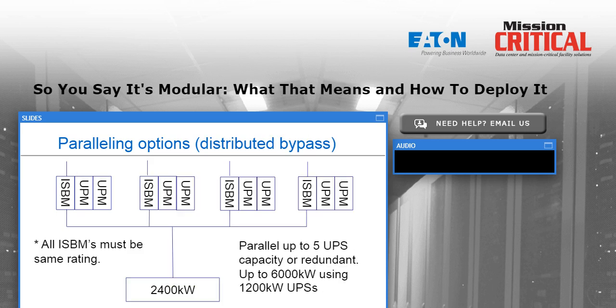Now this last slide here is a block diagram of a distributed bypass system where each one of the 4 UPSs that are shown across this slide has its own independent static switch. So this is the most common way of doing parallel systems for redundancy or capacity today around the world. It does put it in a position where each UPS system does need to be the same size, but these kind of systems, especially if you have 3 or more UPSs in parallel, offer the ability to save significantly on cost of tie cabinetry and cost of the UPS systems and batteries themselves. So we recommend that you consult with your application engineer.